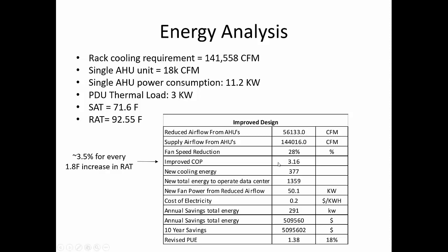Fairly reasonable numbers, fairly reasonable representation. It's a little coarse on the energy analysis, but still serves the purpose quite well for most cases. Again, remember, COP is something that you can spend a lot of time on. And at the end of the day, you will use an average annual COP to do these kinds of calcs.